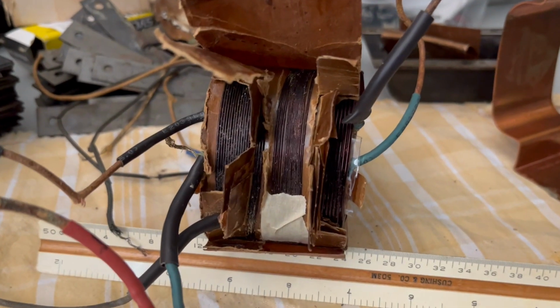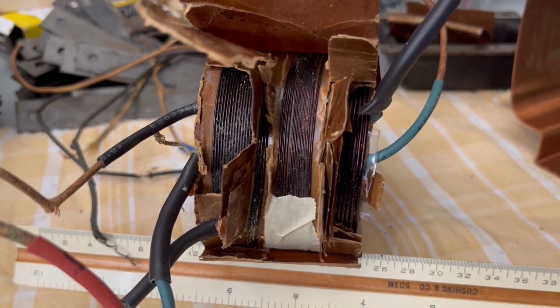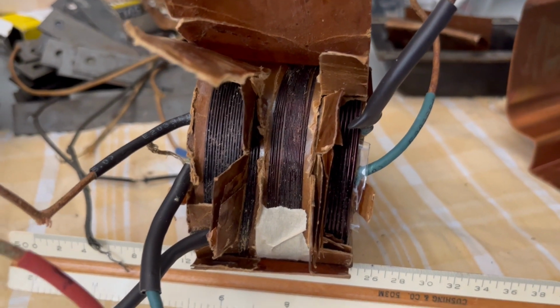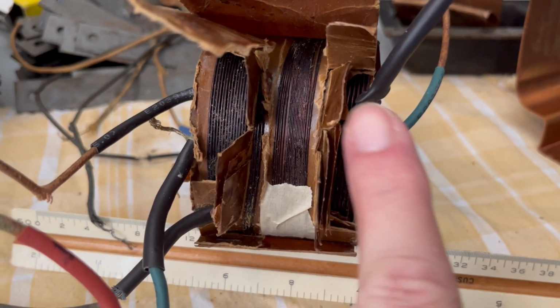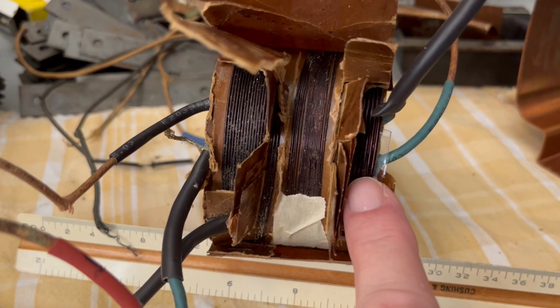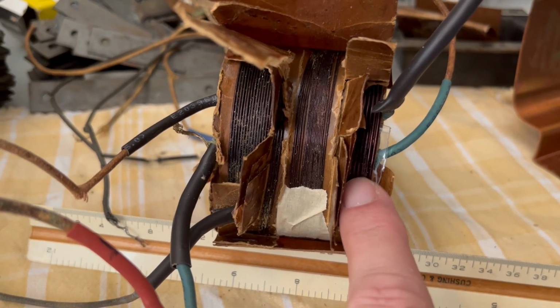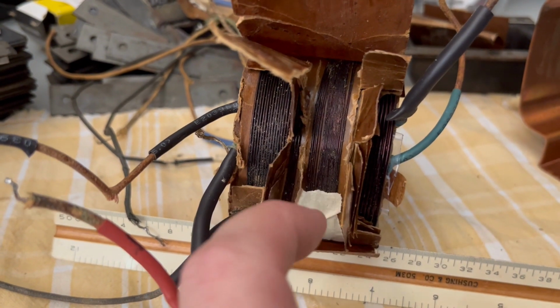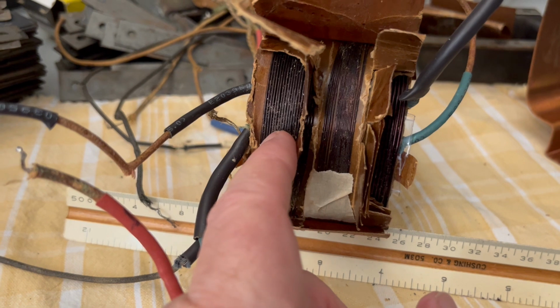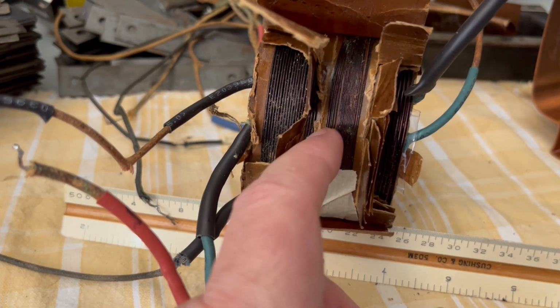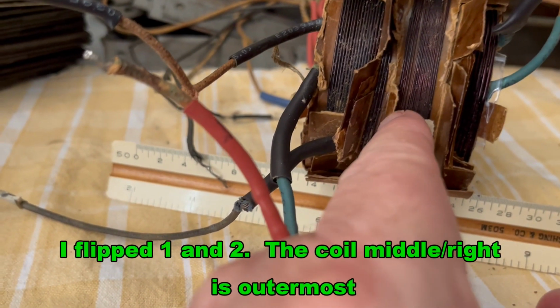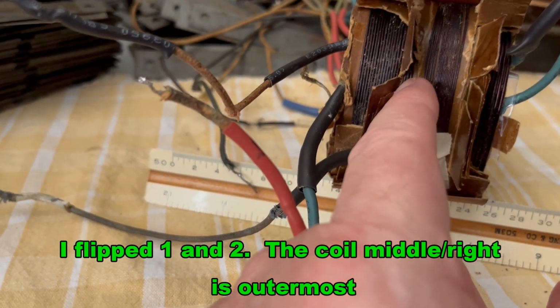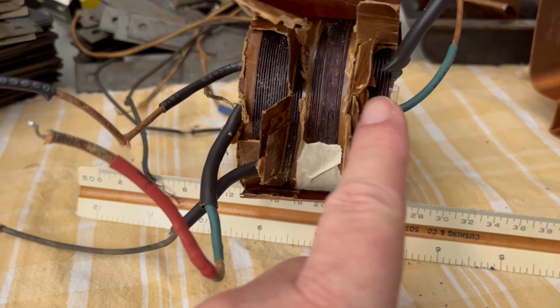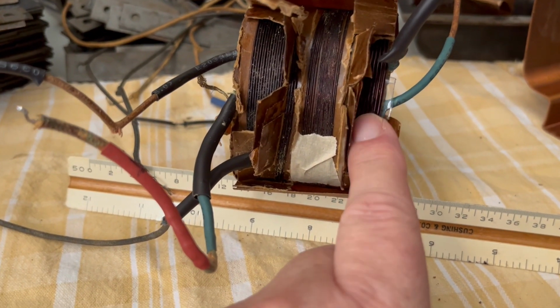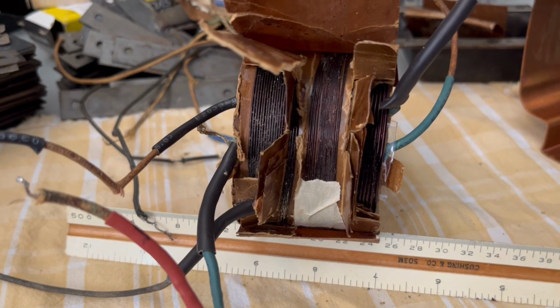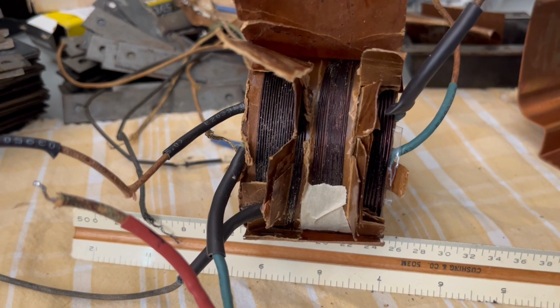And once I tore all of this apart, there's one that's outermost, working to the innermost. In order for me to look at this particular coil, which is the one we're interested in, the one that is shorted with the high voltage coil, I would have to remove, I think this one's the outermost coil, and I can't tell which is which, and then this one must be number 2, and then this one is number 3. And then finally you get to this one. So unfortunately, there aren't that many windings on them.